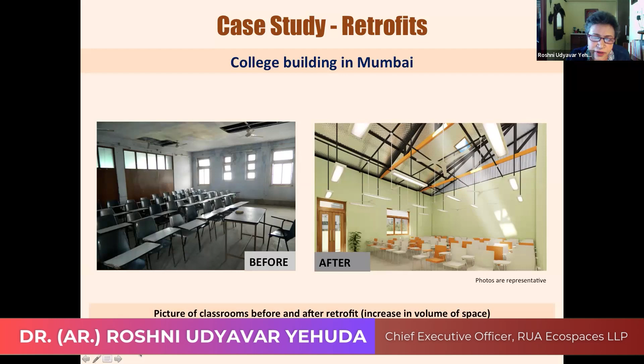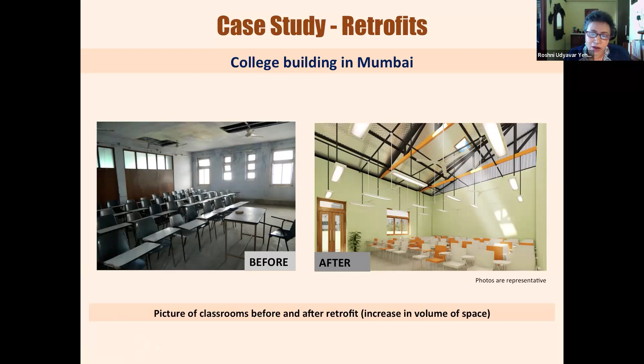There were two, three things. We did the spatial retrofit and structural retrofit of the building, like opening up the windows and removing the false ceilings. But a few things we did were changes in the roof to bring in more light, to have a thermal barrier using a low emissivity material, and we used turbo ventilators to create stack effect. Much of this was also done using simulations.